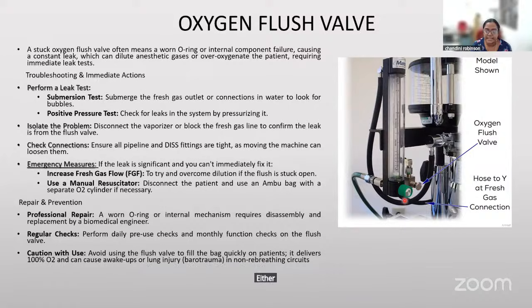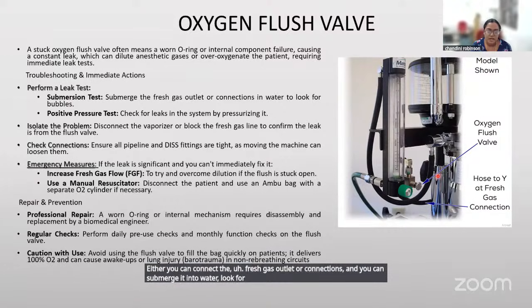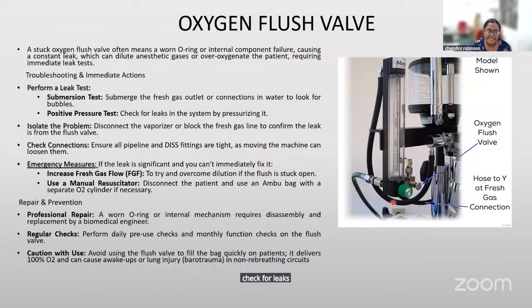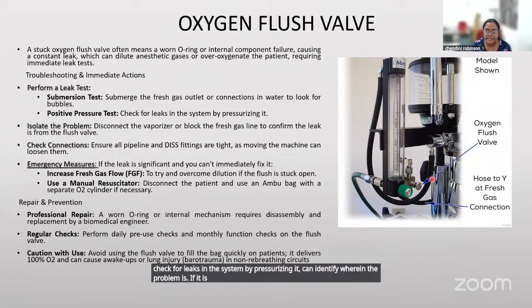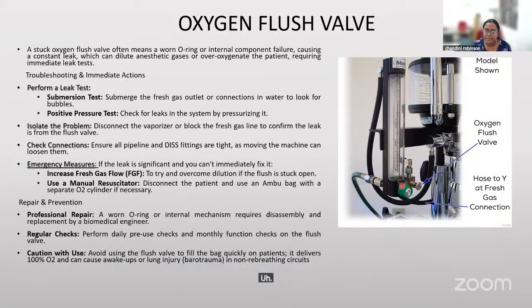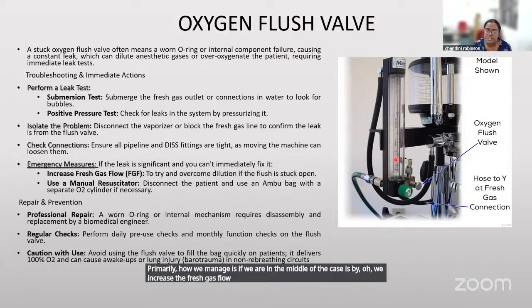Either you can connect the fresh gas outlet connections and submerge it into water and look for bubbles, or check for leaks in the system by pressurizing it. That can identify where the problem is. If it is a worn O-ring, then it requires disassembly and replacement by a biomedical engineer. Primarily, if we are in the middle of the case, we increase the fresh gas flow, or we switch the patient over to an ambu bag and a separate oxygen cylinder if required.